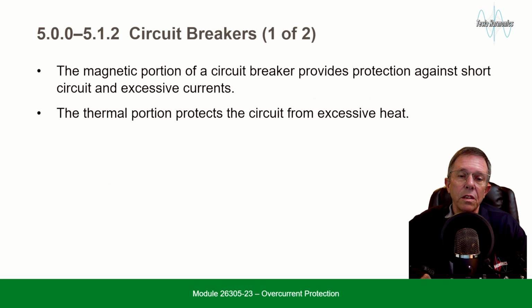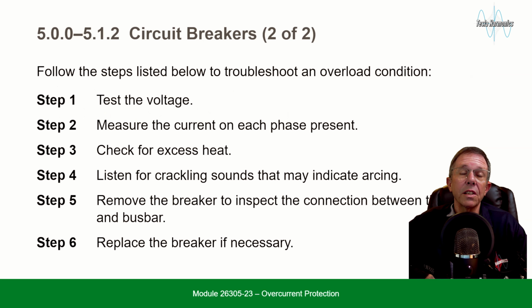The magnetic portion of a circuit breaker provides protection against short circuit and excessive currents. The thermal portion protects the circuit from excessive heat. Follow the steps listed below to troubleshoot an overload condition. Test the voltage, measure the current of each phase present, check for excess heat, listen for crackling sounds that may indicate arcing, remove the breaker to inspect the connection between the breaker and the bus bar, and replace the breaker if necessary.